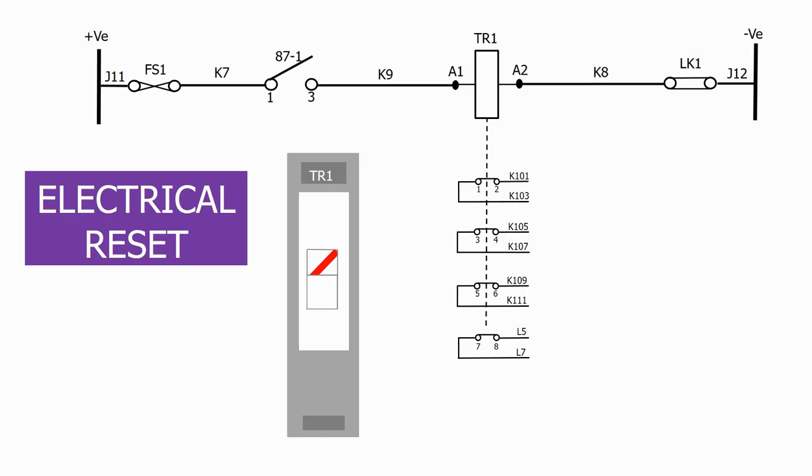To reset the contacts and the flag, we need an external signal. This can either come from the SCADA system, a signal from a timed reset circuit on the panel itself, or from a push button mounted on the relay panel.